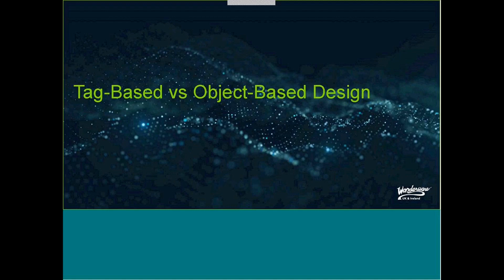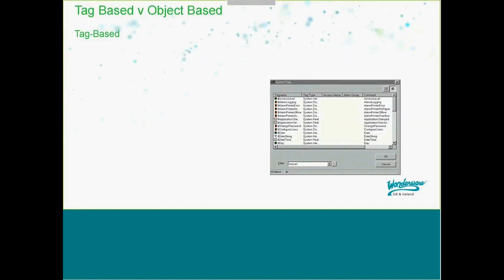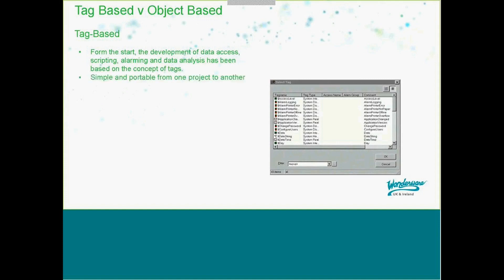Let's have a look at tag-based and object-based design in general. From the inception of PC-based HMI and supervisory products, the development of data access, scripting, alarming, and data analysis has been based on the concept of tags. Although this approach can be simple and portable from one project to another, a tag-based environment uses a flat namespace, which can be a shortcoming because individual elements can't be linked or organized into a more intelligent structure with built-in relationships and interdependencies.